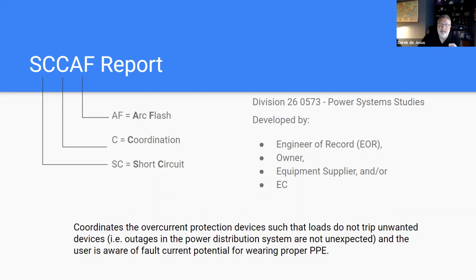The most important activity in my mind is getting the study prior to doing the NETA testing, and that should be called out in the specifications as a design review comment if it's not already there. The reason you want that is because it's an opportunity for you and the contractor to save time. They can set the breaker correctly, the relay correctly, test it for that setting, verify it against the time current curve for that device, and validate its accuracy once and for all. If we don't have the SCCAF report at that time, we might have to do multiple tests, at a low value and a high value, so that when we do get the study, we just set it and hopefully it falls within that curve.